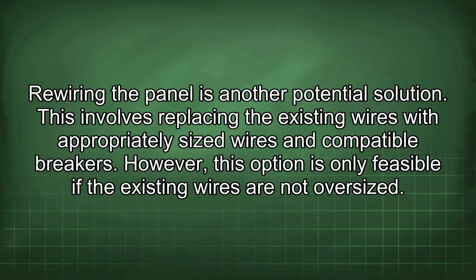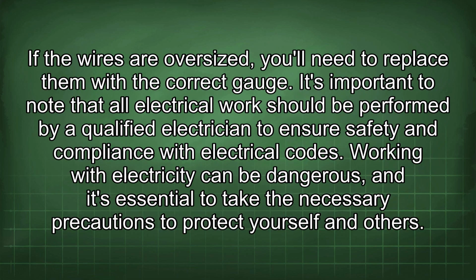Rewiring the panel is another potential solution. This involves replacing the existing wires with appropriately sized wires and compatible breakers. However, this option is only feasible if the existing wires are not oversized. If the wires are oversized, you will need to replace them with the correct gauge.